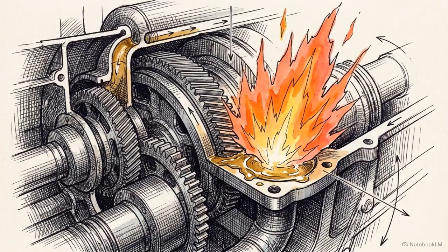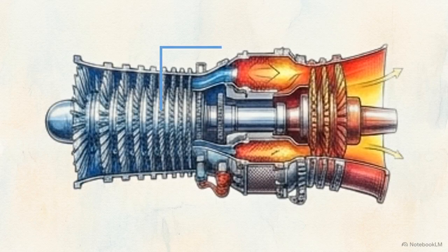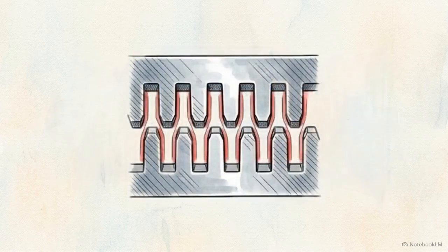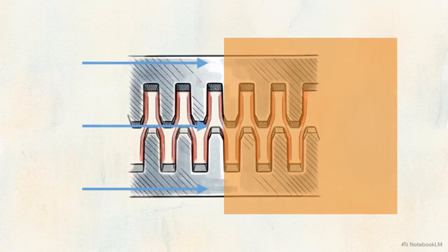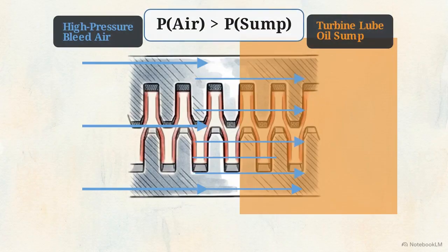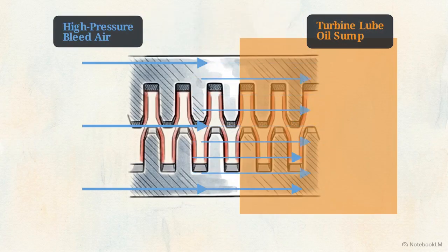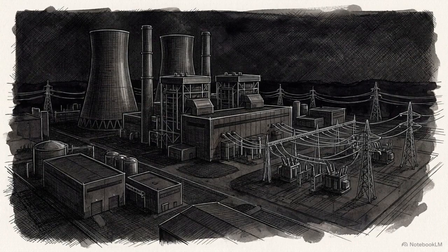If the oil weeps past the seals, it creates an internal fire risk. Sump pressurization solves this by bleeding high-pressure air from the compressor to create a wall of air against the bearing seals. This air pressure is kept slightly higher than the internal sump pressure, forcing any leakage inward rather than letting oil escape.